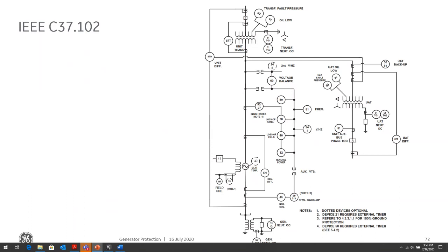Whether you use the 51V or the 21 will depend on the impedance that you have to read. So if the impedance is really small, you might not be able to set the distance, and the only option is to set a 51V. And with the 51V, as Terry mentioned, it's looking at voltage collapse as well as current. So in that case, you might have a low current, but since the voltage has collapsed, you can still operate with that element. Whereas for high loading conditions, your current can be above the pickup of the 51V, but because you're in a normal condition, your voltage is not low, as in the case of a phase to ground fault, so you will be restrained from tripping.